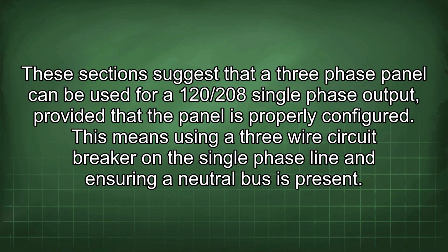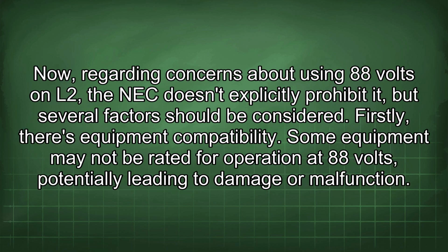These sections suggest that a three-phase panel can be used for a 120/208 single-phase output, provided that the panel is properly configured. This means using a three-wire circuit breaker on the single-phase line and ensuring a neutral bus is present. Now, regarding concerns about using 88 volts on L2, the NEC doesn't explicitly prohibit it, but several factors should be considered. Firstly, there's equipment compatibility. Some equipment may not be rated for operation at 88 volts, potentially leading to damage or malfunction.